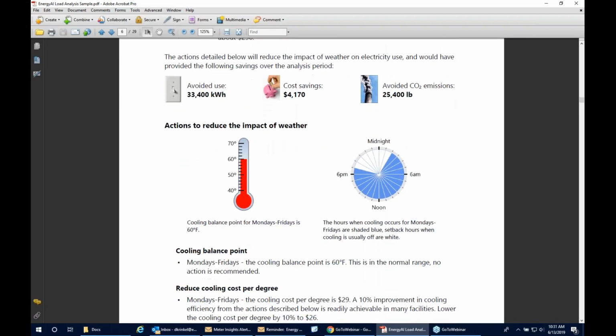We also do another slightly non-standard analysis, although I guess it's becoming more and more standard now. We also try to look at an hour-by-hour basis how weather affects the usage. And here we use a very low threshold of correlation. We do a regression on each individual hour, but we don't use that to establish whether there is a solid regression or not. We look at the whole day. But here we're just trying to see, can we tease out any evidence of a setback?